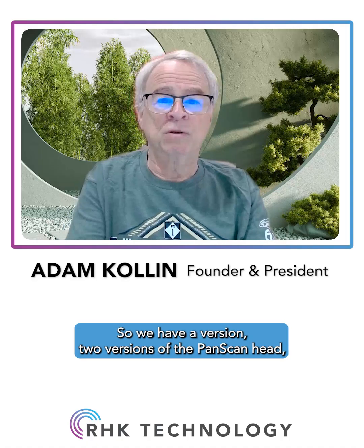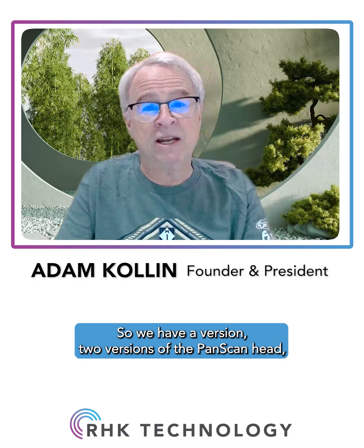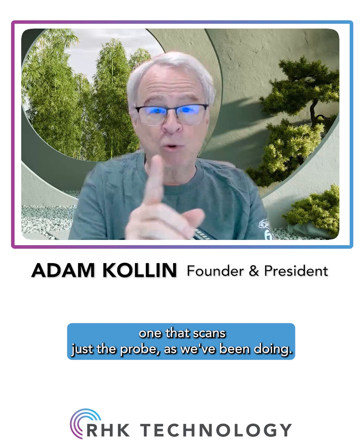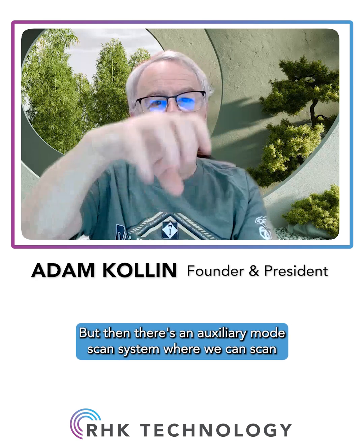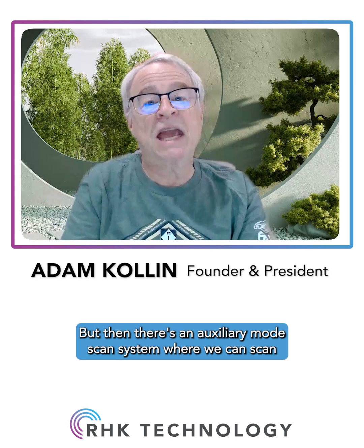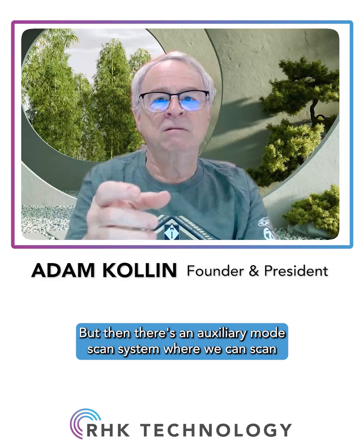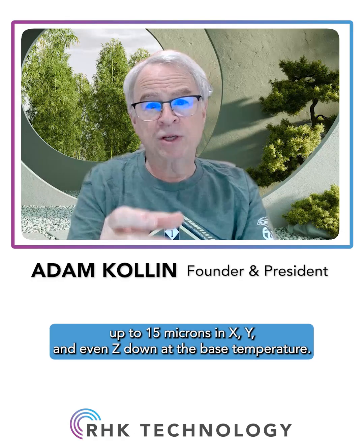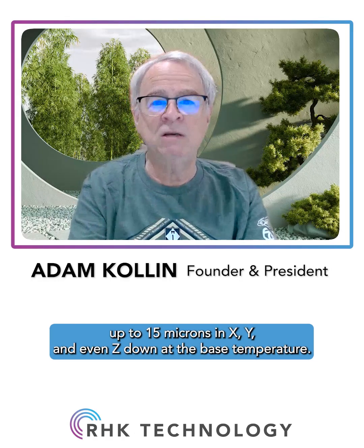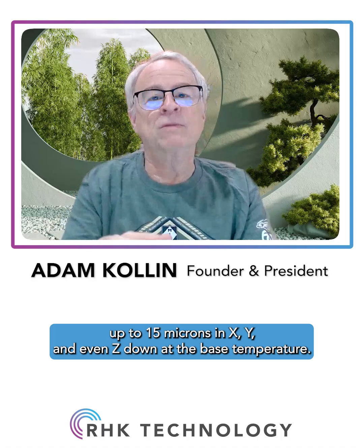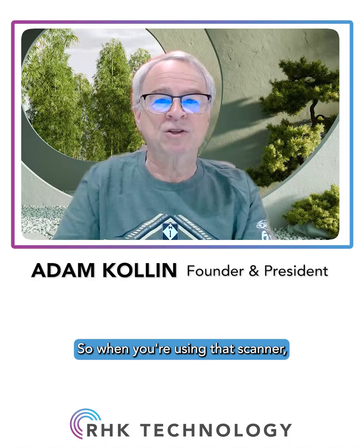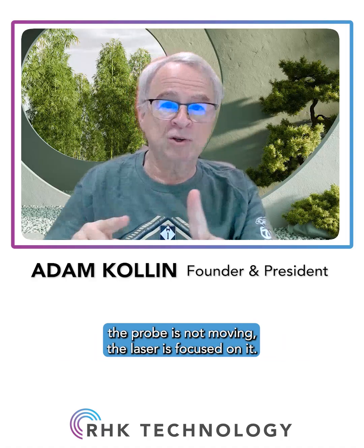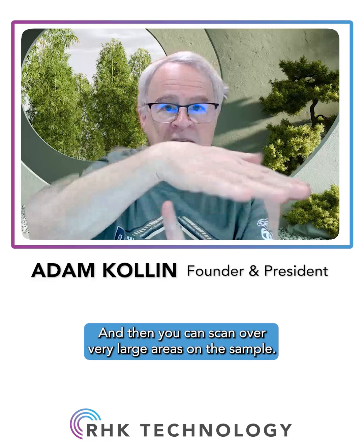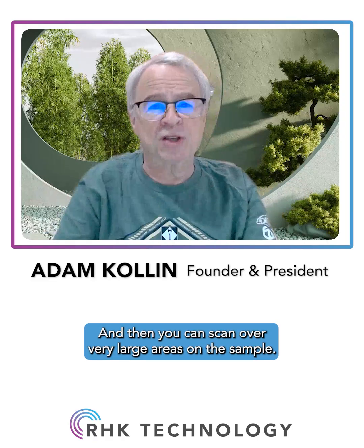So we have a version, 2 versions of the PanScan head, one that scans just the probe, as we've been doing, but then there's an auxiliary scan system where we can scan up to 15 microns in X, Y, and even Z down at the base temperature. So when you're using that scanner, the probe's not moving, the laser's focused on it, and then you can scan over very large areas on the sample.